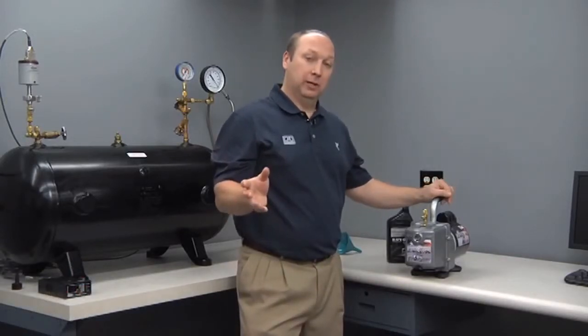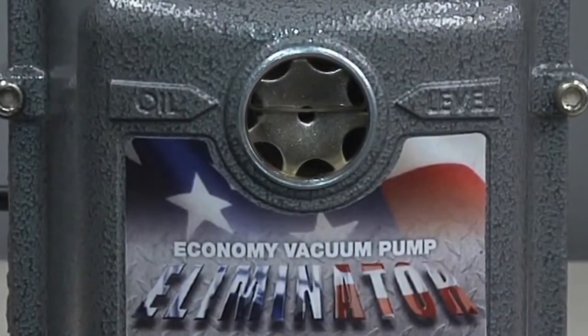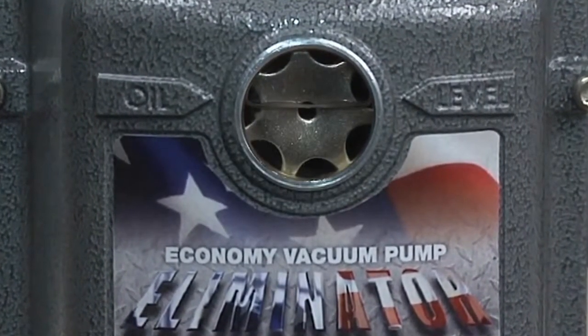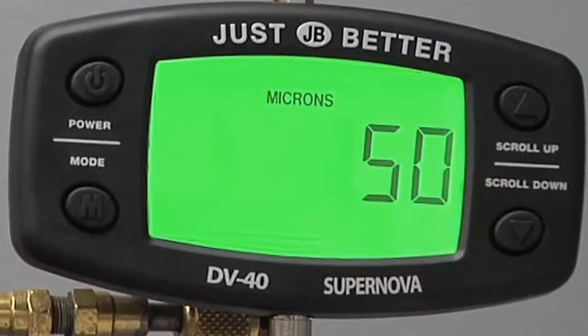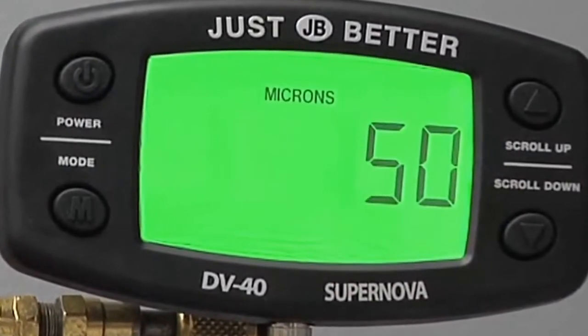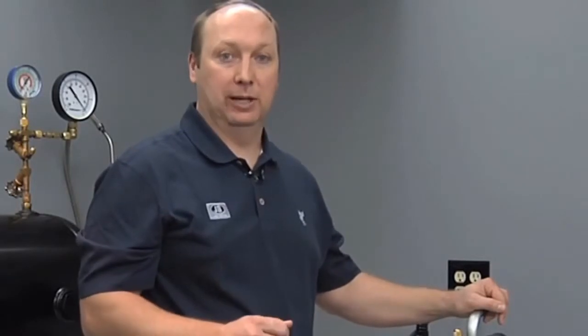If you're unsure if you're ready for an oil change and you can't tell by looking through the sight glass, we recommend attaching a micron gauge directly to the pump. If you achieve 50 microns or better, your oil is still good. If not, it's time for an oil change.